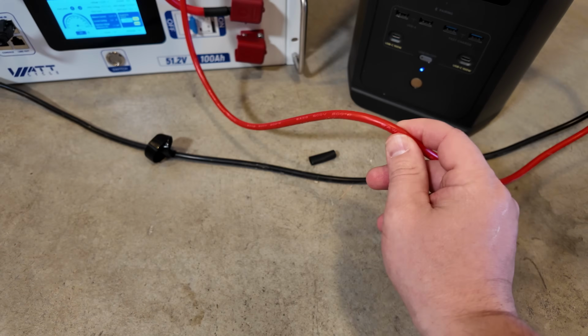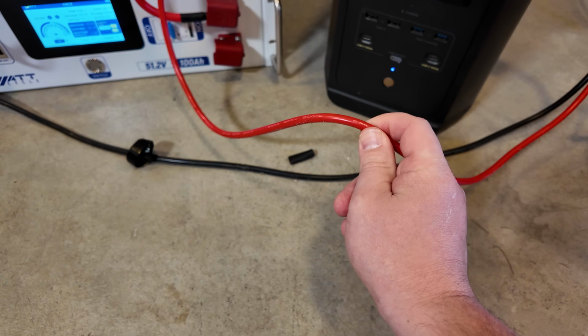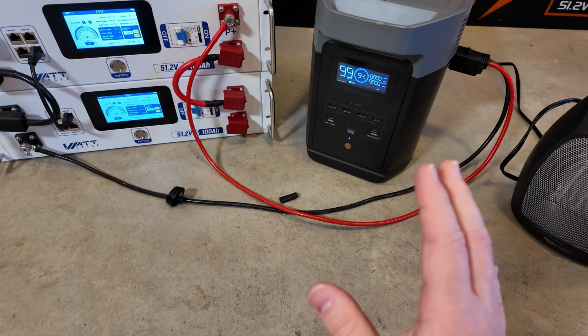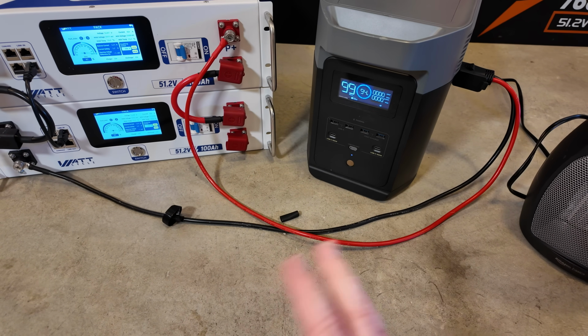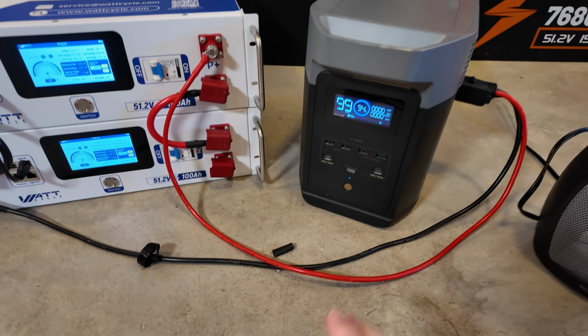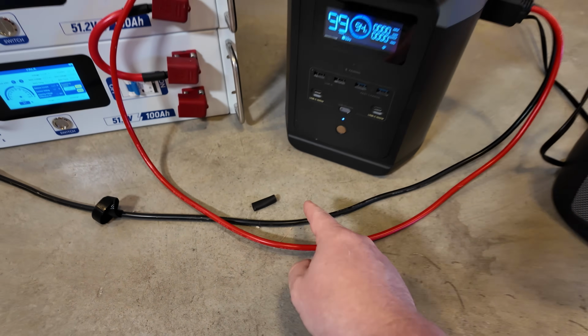8 gauge cable with a 200 degree Celsius insulation value is really only good for around 80 amps max, and that's pushing it. So you have the potential to overload this wire if there's a dead short inside one of these units and nothing to trip off.